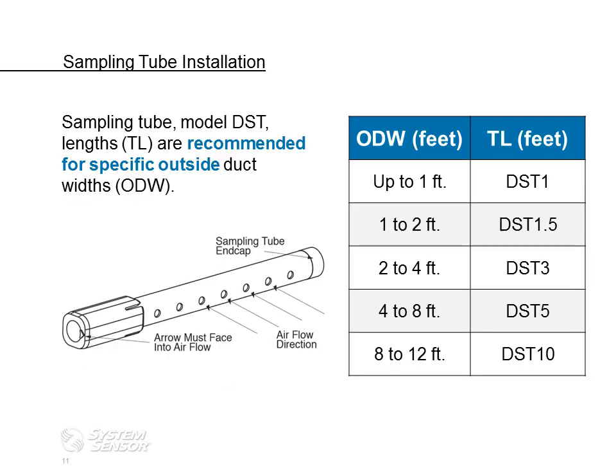The sampling tube installation. Our sampling tube model is DST, followed by a number for the length of the sampling tube. They are recommended for specific outside duct widths, or ODW. Up to 1 foot, we recommend a DST1. 1 to 2 feet is a DST1.5. 2 to 4 feet is a DST3. 4 to 8 feet is a DST5. And 8 to 12 feet is a DST10.